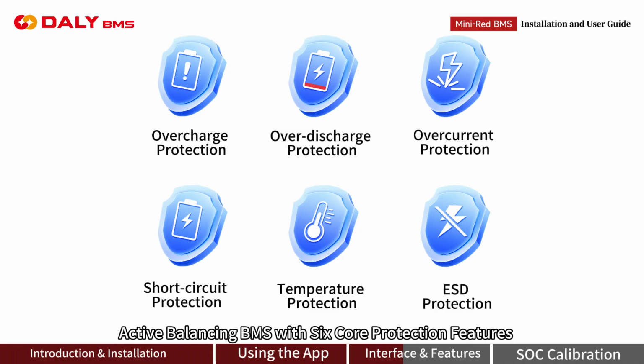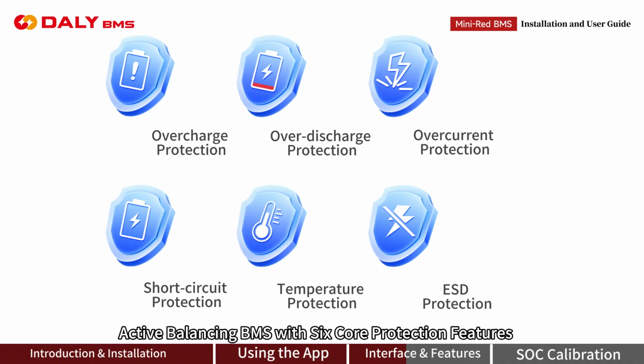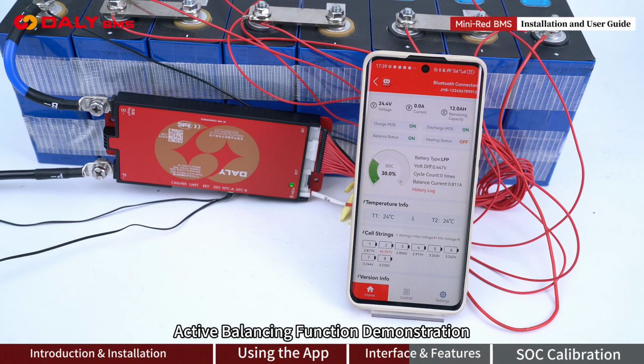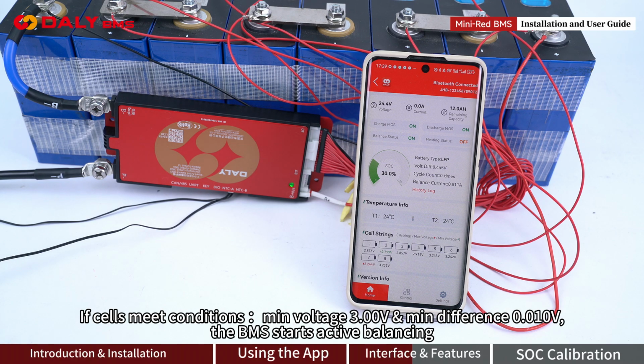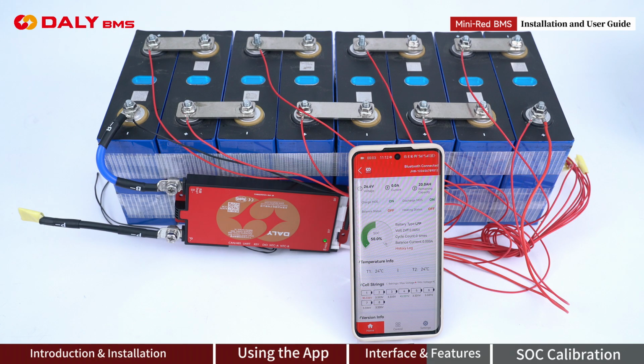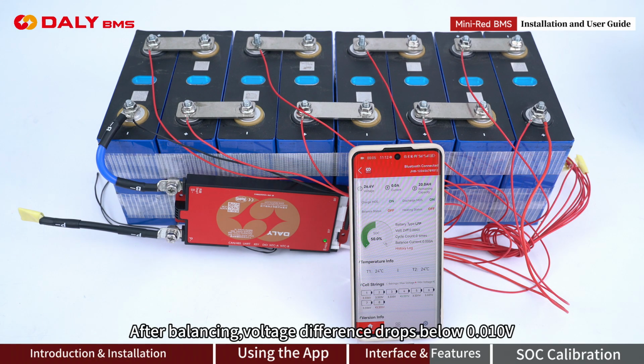Active Balancing BMS with 6 core protection features. Active Balancing Function Demonstration. If battery meet conditions min voltage 3.00 volt and min difference 0.010 volt, the BMS starts active balancing. After balancing, voltage difference drops below 0.010 volt.